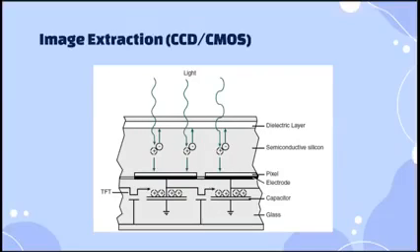So for the CCD and CMOS na what we call this detector, when light photons enter the silicon layer, ionization of the molecules separates electrons from them, leaving positively charged electron holes behind. So almost the same with the amorphous selenium, no, direct radiography. However, a layer of microscopic electrodes beneath the silicon is given a negative charge. Okay? So same pa rin sa direct radiography. So may negative charge dito so that it can attract the positively charged electron hole.